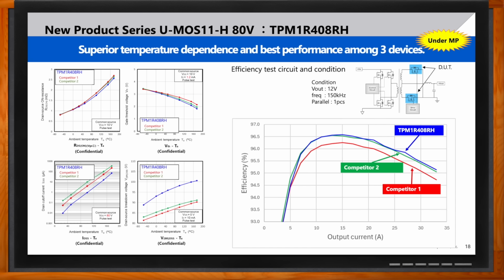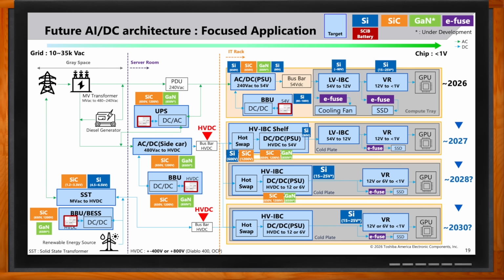Jake, walk me through a typical application. This is one of the best applications to look at: data center and AI data center—you probably can't stop hearing about it, and Toshiba hasn't stopped thinking about it either. Simply put, you go from high voltage at the grid down to what will be 800 volts in the future, then 800 to 54 volt, and 54 to 12 volt. Every step requires conversions. We'll focus on the conversions from 800 to 54, and 54 volt to 12. If you improve efficiency on these subblocks—what we call high voltage IBC and low voltage IBC—it pays dividends, generating less heat and improving overall efficiency.